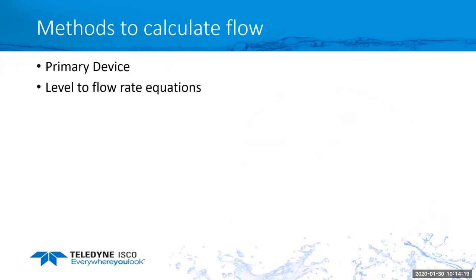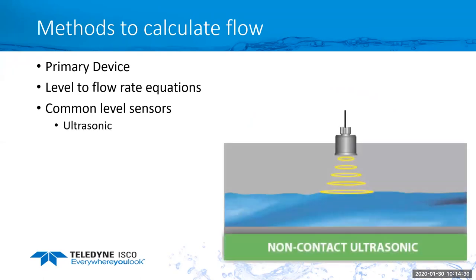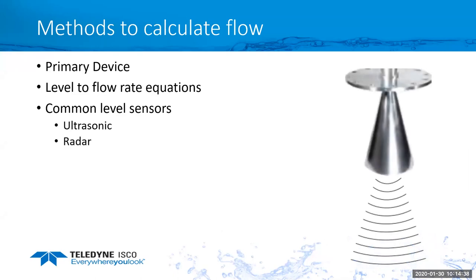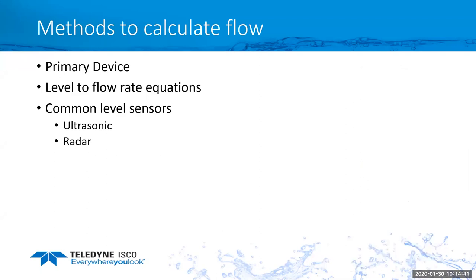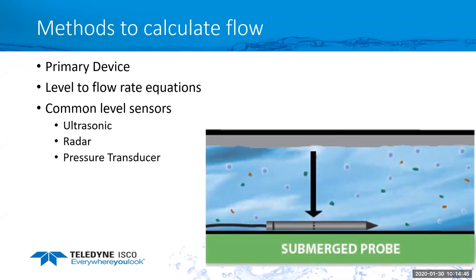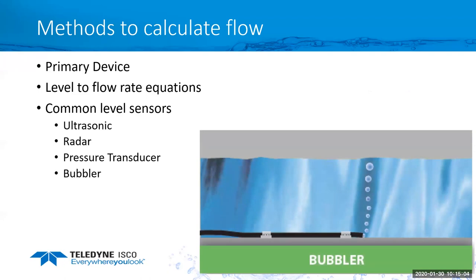So calculating flow with a primary device requires a level-to-flow equation. There are common level sensors that are used with the weirs and flumes. You can use an ultrasonic sensor, which is non-contact, mounted above your flow stream, so you don't have to worry about debris getting caught in the sensor. There are radar level sensors that also mount above your flow stream. Or you can use a pressure transducer. A pressure transducer is mounted on the bottom of your channel. When you order a flume, you just tell your vendor what type of technology you plan on using, and they will usually accommodate you to set up the appropriate level technology to work with it. And you can also use a bubbler. The way a bubbler operates, it measures the amount of pressure it takes to push out one bubble at the end of that bubble line, which would be equivalent to the water depth.